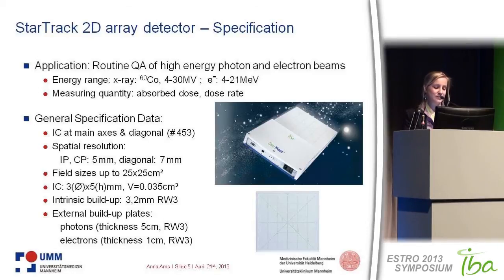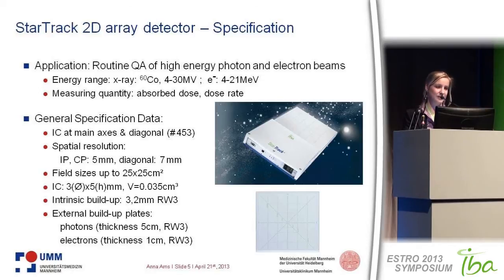There are two different build-up plates: a five centimeter thick photon build-up plate and a one centimeter thick electron build-up plate, which come with the detector.